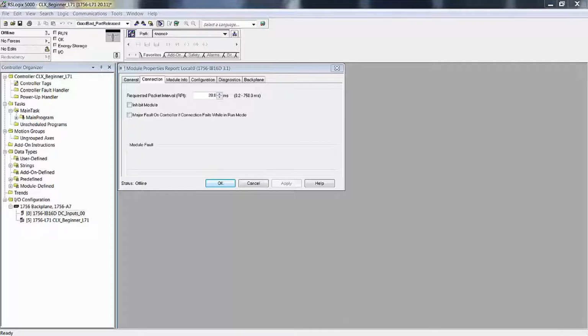You need to think of the backplane on a 1756 chassis as a 32-bit parallel network instead of a serial network like Ethernet or RS-232. Well, RS-232 is not a network, but it's serial. It means you have one line level that goes up and down at a baud rate to communicate. So you only communicate one bit at a time.